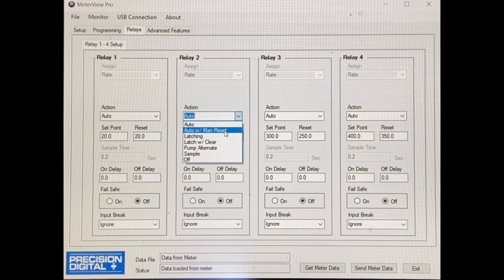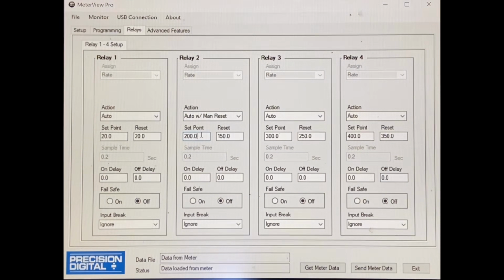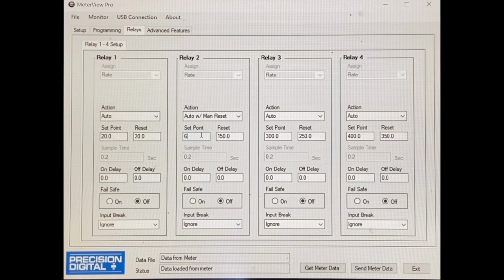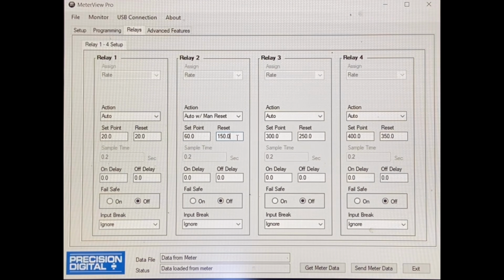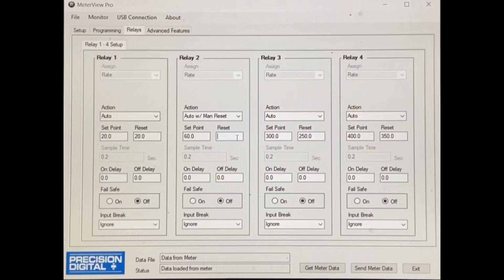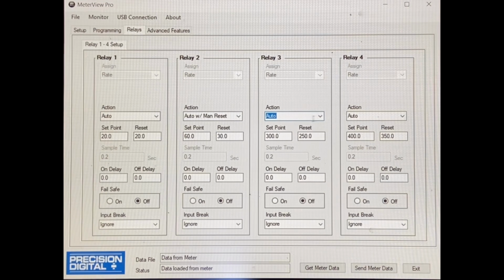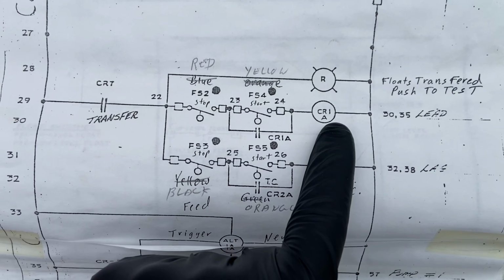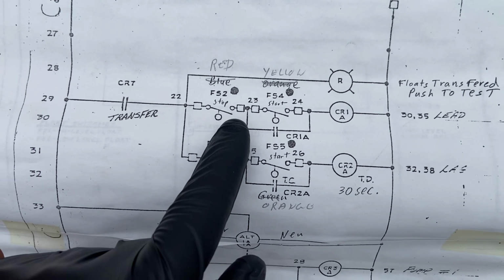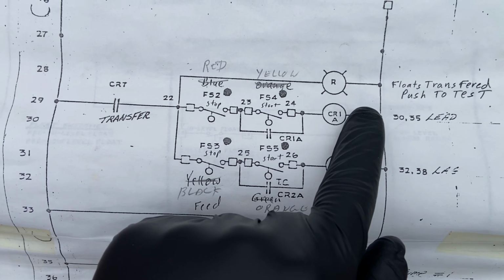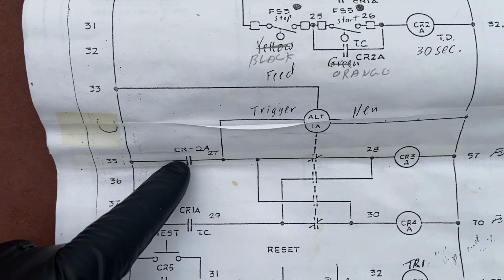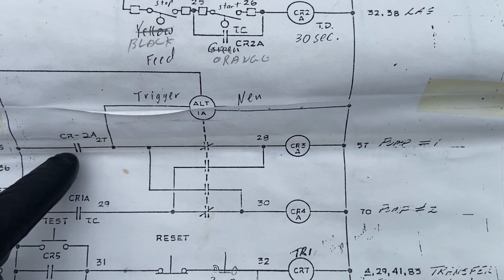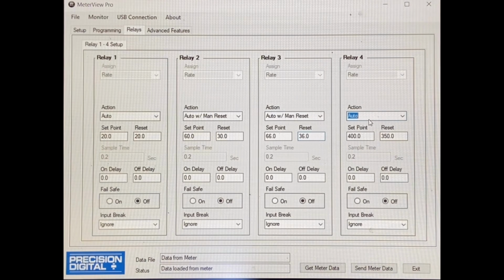In terms of relay 2 and 3, that is our lead and lag system, and we are going from 2 floats to a single relay. And we're able to do that because the precision digital can latch itself in, just like that latching circuit. And that is how we get our auto with manual reset, and that is why we have a set and a reset. Our set is our start, and our reset is our stop, and that gives us an actual pumping range. That is what our CR1A and our CR2A used to do. Their whole purpose was to latch in and give you a range. We are getting rid of that and just going straight to the alternator with our precision digital relay.